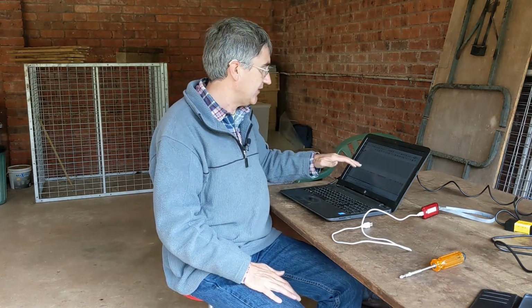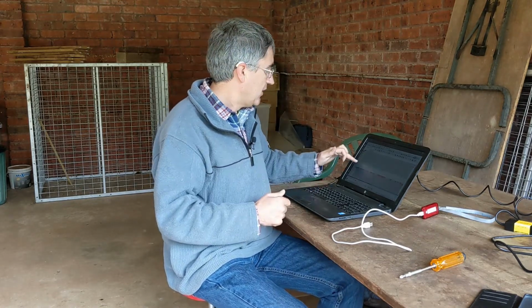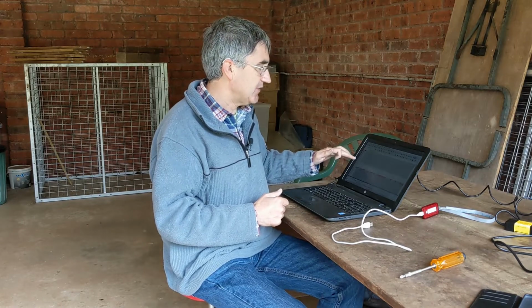That says to me that the master unit was receiving bad packets of data and therefore not sending them onto the computer. Adds up to be about 18 seconds worth of data as I'm accelerating, so it's a reasonable amount. I was accelerating for probably about that amount of time, that sounds right. It was up a hill, I wasn't accelerating really hard, but maybe drawing about 200 amps, something like that.